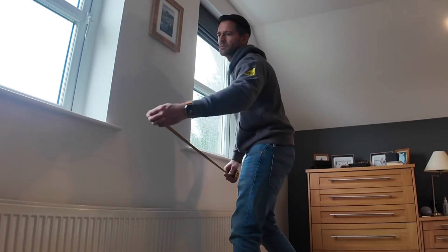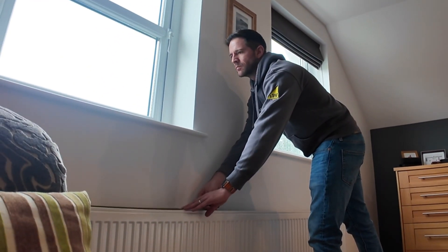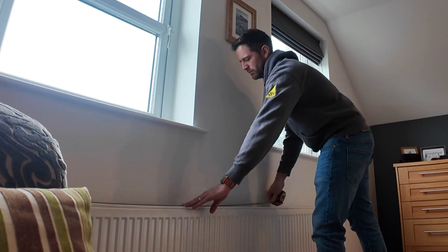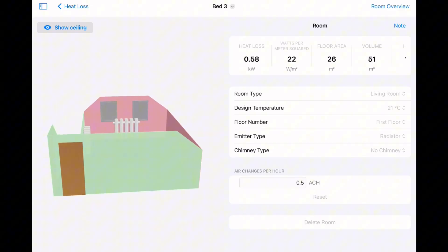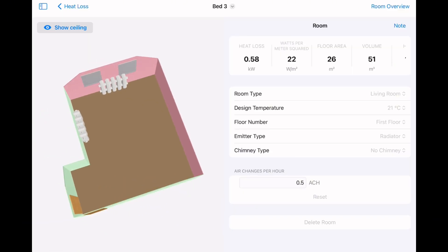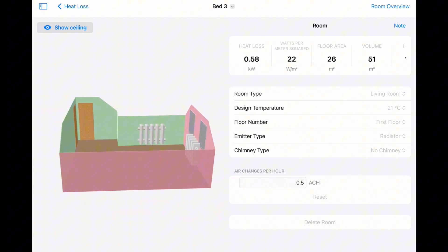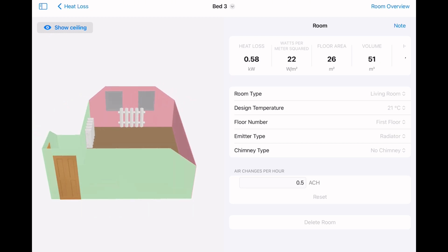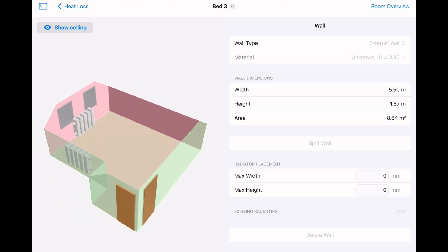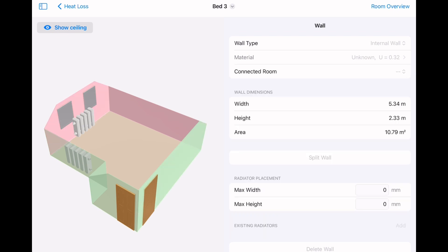We then measure the size of any radiators in the room and add them to the corresponding walls. Once the scan is complete, the software generates a 3D model of the room where all of the different surfaces can be edited to change their construction type and U-value. A total heat loss figure for the room is then calculated.